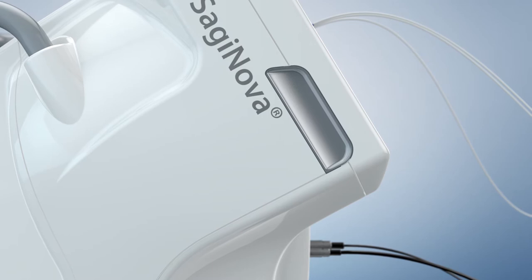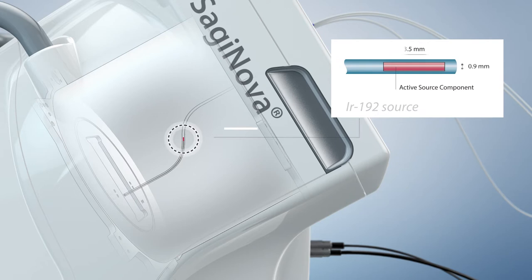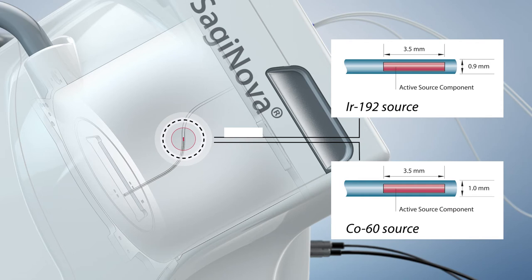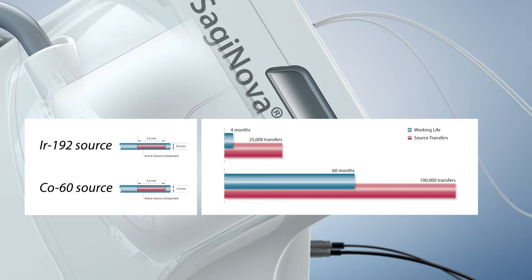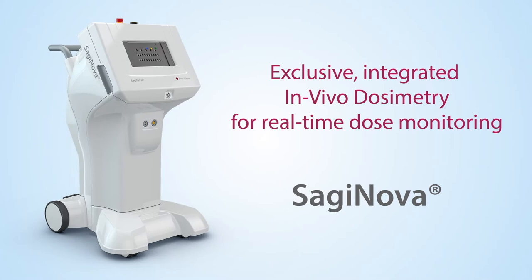Eckert & Ziegler BEBIG exclusively provides the unique choice of two isotopes, Iridium-192 and Cobalt-60. The high quantity of source transfers and the long working life of the miniaturized Cobalt-60 source reduce time for source exchange logistics and increase valuable clinic uptime.